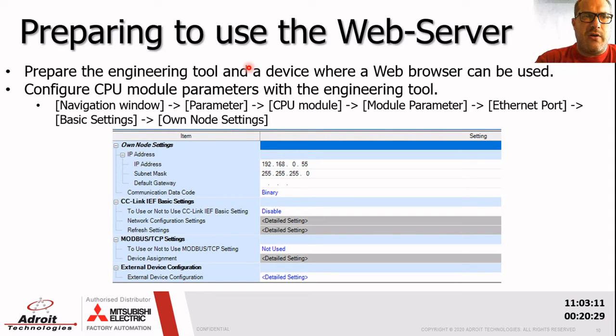Normally you open a new program, and to change the actual parameters in the IP address, you go to navigation window, parameter, CPU module, module parameter, Ethernet port, basic settings, and own node settings. Then inside there you can change your IP address.